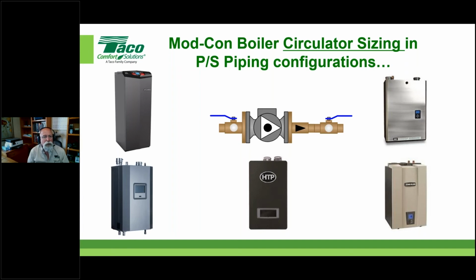The only thing that would come to counter that, not counter it, but just say, remember that we want to keep it at 2 feet per second or slightly higher for the bubbles, et cetera. But again, folks, I talk about if you do a really good job of the initial purging of the big bubbles, the micro bubbles and the tiny bubbles aren't what really hurt us. It's when we get a call and they say this pump's not working or the boiler's going off on high limit, et cetera, it's because it's full of air and no one did the initial purge.